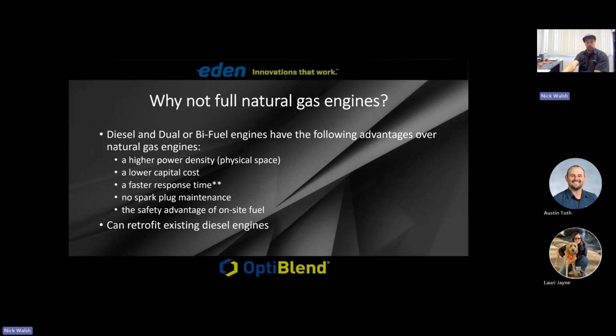In hospitals, for instance, there's a mandate that in a power outage, the generators need to come online and grab the bus in, I think, 10 seconds or less. Most natural gas engines, or at least at the time, couldn't meet that response time. So they would have a diesel engine on standby that comes online, grabs the bus in 10 seconds, and then sheds that load to the full gas engines.